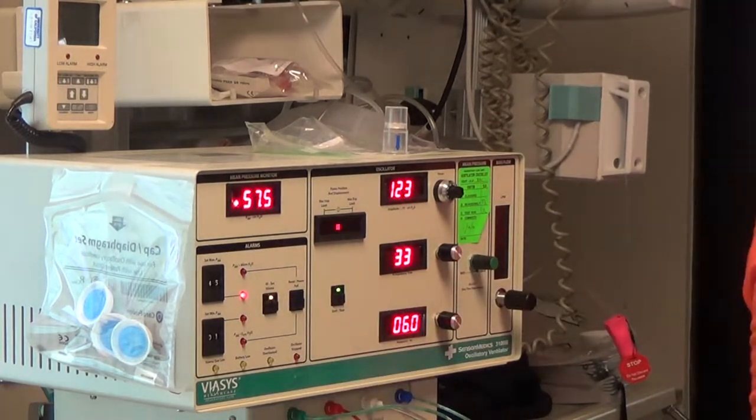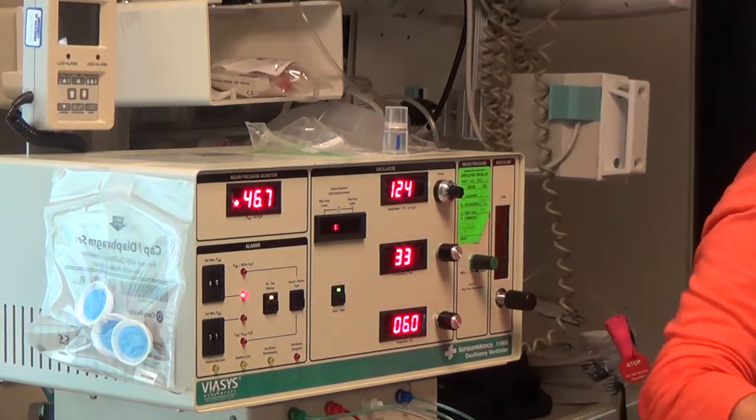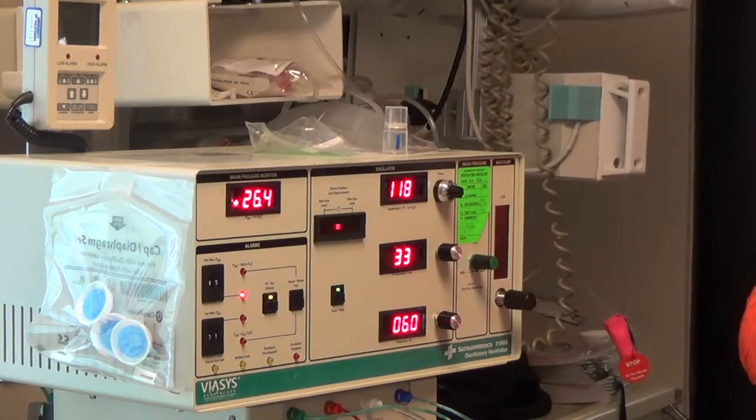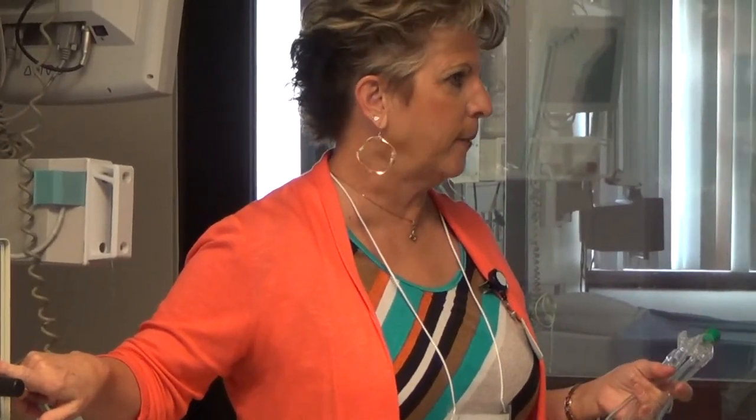So, pneumothorax, obstruction. What it does is it's dumping to this dump valve. So the patient, if he were waking up, he's kind of breathing ambient air, but he's also going to get a pneumothorax, right? So this is not enough flow to sustain spontaneous breathing. That's exactly why we knock these patients out, we paralyze them, okay? So you need to figure out what's going on with the patient in order to fix that, okay?